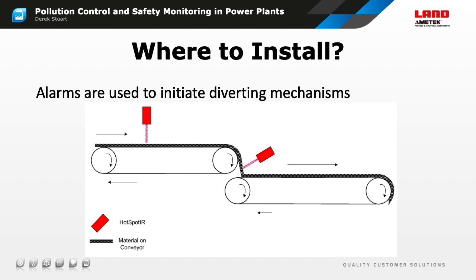It's important to choose the correct installation location for the scanner. The most obvious is directly above the conveyor, looking down, but mounting at a transfer point allows it to see further into the material as it fans out, and the increased exposure to air can also cause the temperature of any hotspots to increase. So summing up, a hotspot detector is a rapidly responding sensor which can identify hot, smouldering material on a moving conveyor with very high spatial resolution. A simple signal processor can reduce a lot of data to a single number, or it can be connected to a full-featured image processor for more in-depth analysis.